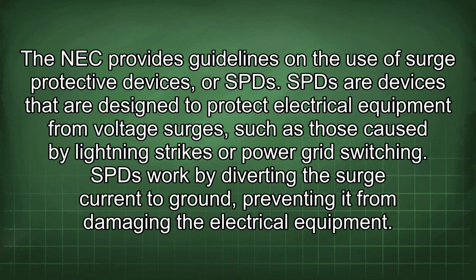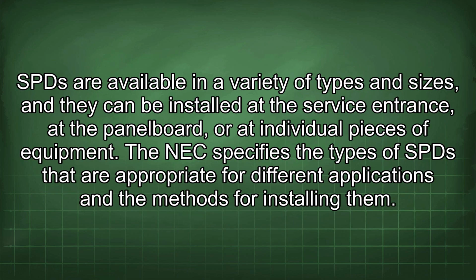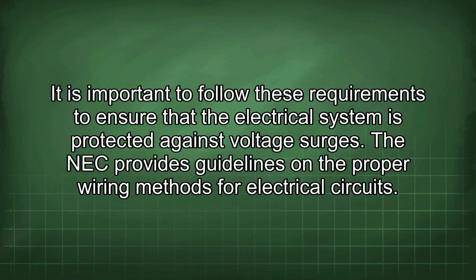The NEC provides guidelines on the use of surge protective devices, or SPDs. SPDs are devices that are designed to protect electrical equipment from voltage surges, such as those caused by lightning strikes or power grid switching. SPDs work by diverting the surge current to ground, preventing it from damaging the electrical equipment. SPDs are available in a variety of types and sizes, and they can be installed at the service entrance, at the panel board, or at individual pieces of equipment. The NEC specifies the types of SPDs that are appropriate for different applications and the methods for installing them. It is important to follow these requirements to ensure that the electrical system is protected against voltage surges.